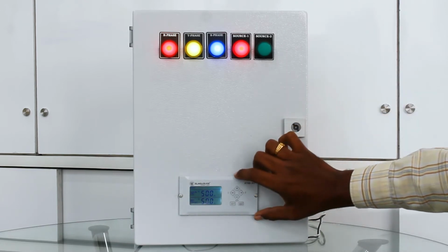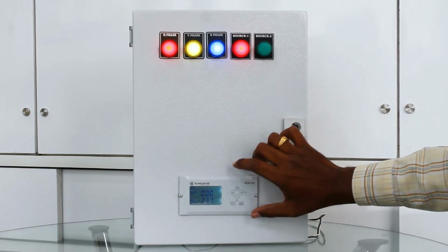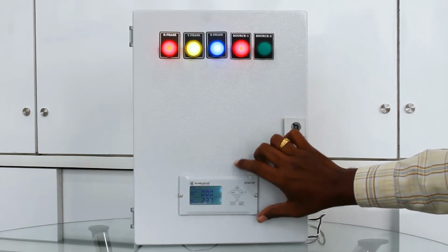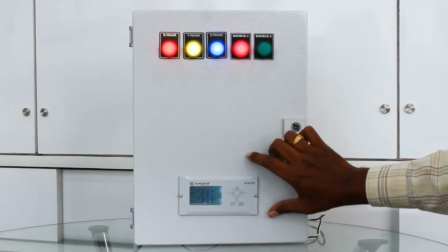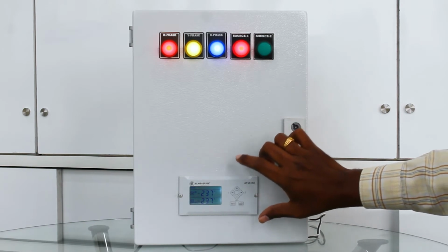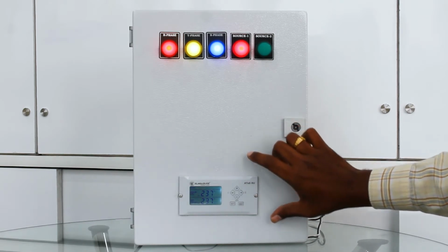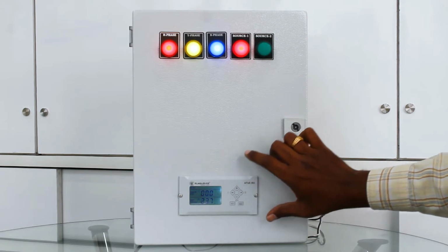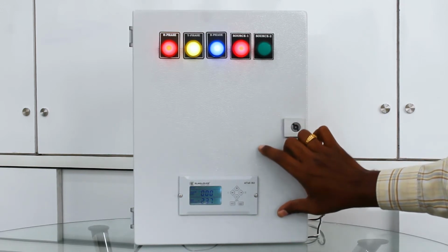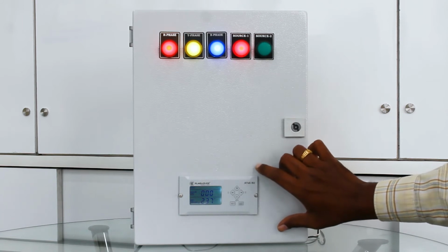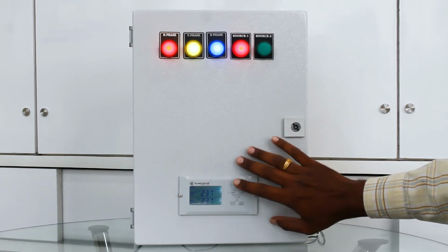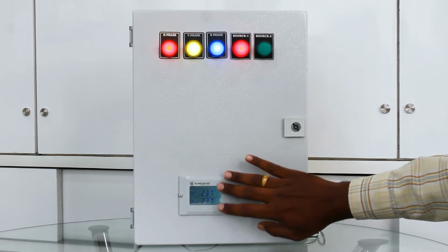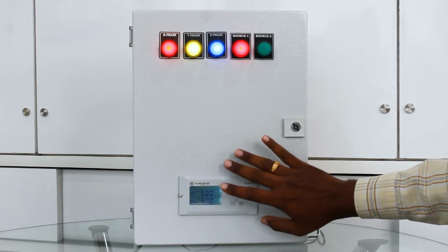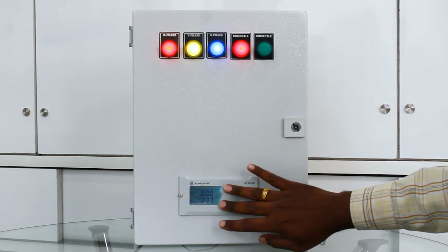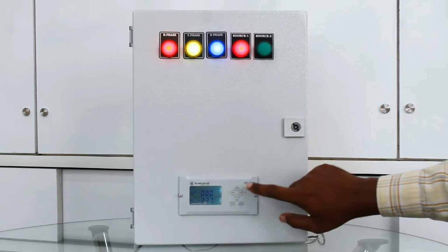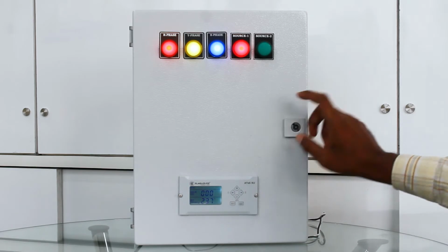And this is our remote display. Through this remote display, we can program all electrical parameters for the transformer as well as the generator: voltage thresholds like under voltage, over voltage, under frequency, over frequency, phase sequence enable and disable, transfer delay, and recovery delay. So all programming parameters can be set, and we can also use it as a multifunction meter. Here we can monitor the 3-phase transformer as well as generator line to neutral voltage, and also see in which position the ATS is, either EB or DG position.